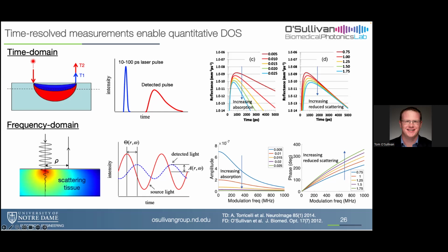And I should point out, you're not just doing this with one laser pulse. You're doing this at a 10 megahertz repetition rate and collecting data for 5 seconds. The reason you have to do that is because you build up this curve essentially statistically. Every pulse, you might get a few dozen photons or something, and you plot them where they are. Then you do that again and again and again, following the repetition rate.